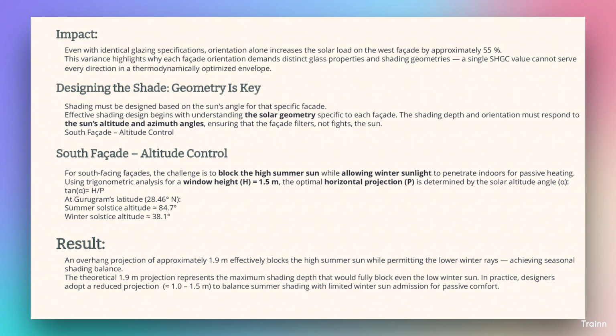Impact: even with identical glazing specifications, orientation alone increases the solar load on the west facade by approximately 55%. This variance highlights why each facade orientation demands distinct glass properties and shading geometries. A single SHGC value cannot serve every direction in a thermodynamically optimized envelope. Designing the shade geometry is key. Shading must be designed based on the sun's angle for that specific facade.